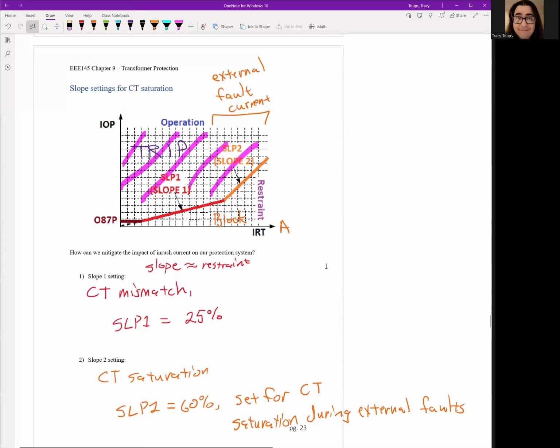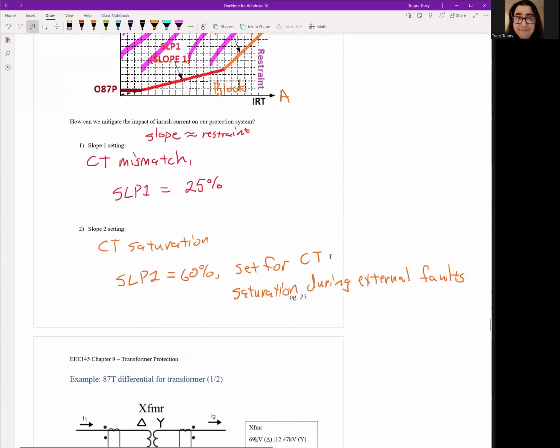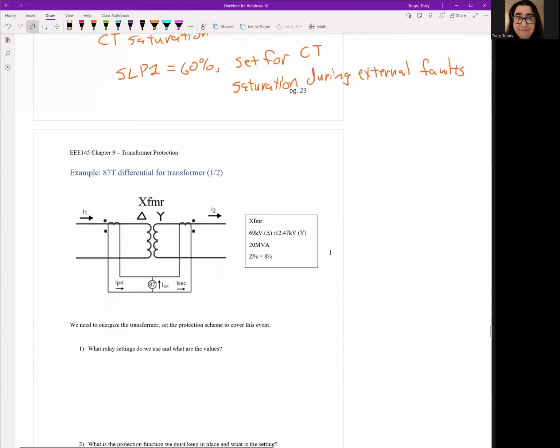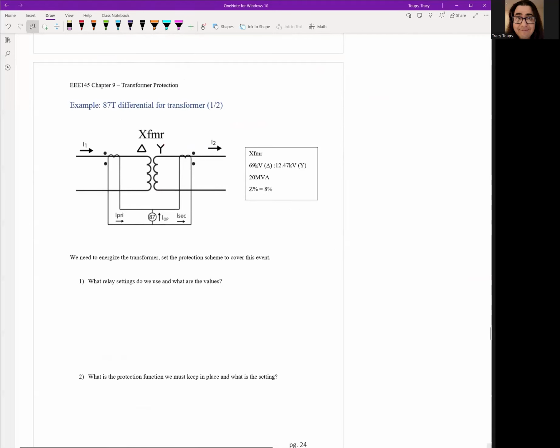Okay. So just remember slope 1, CT mismatch, slope 2, CT saturation. Okay. And those percentages are pretty common. You usually don't deviate from that. I would say if you're deviating away from 25 and 60%, you should have a pretty good compelling reason not to. This is not something that just like, oh, well, let's just do 120% today, right? Because then nothing's going to work. Okay. There's a reason why we have recommended settings.